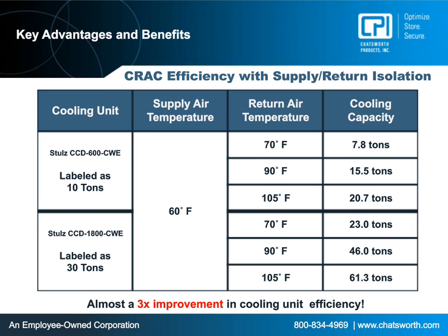So I knew that we can shut down CRAC units as soon as we get that delta T up in that data center. And that's exactly what we did. We partitioned the air. We didn't do anything crazy. We didn't do doors at the end of the rows. We just helped them in their cabinets and above their cabinets, and we were able to raise their delta T up at least 18 degrees to get them to shut off 4 CRAC units.